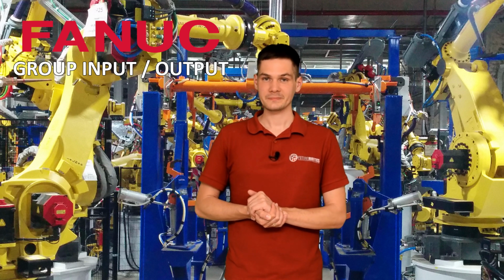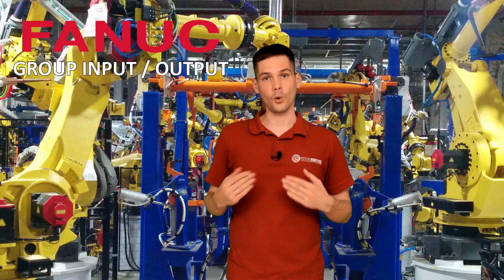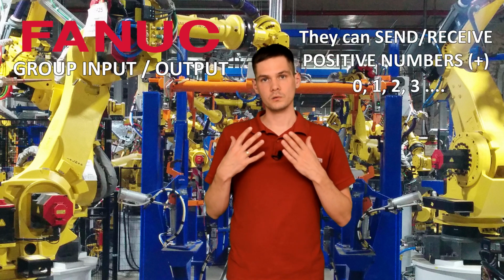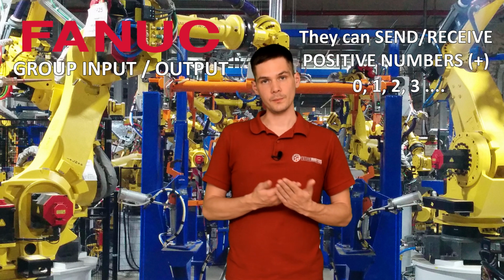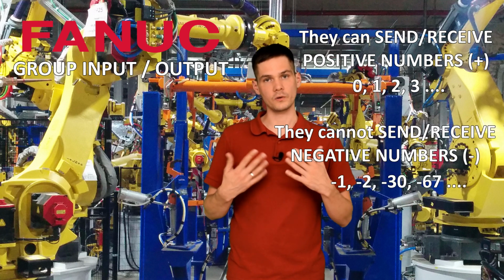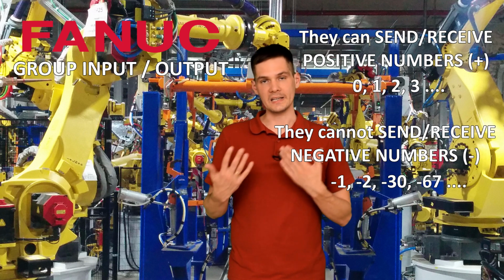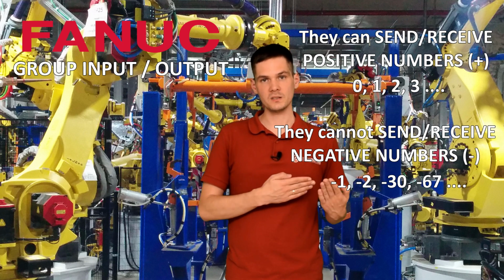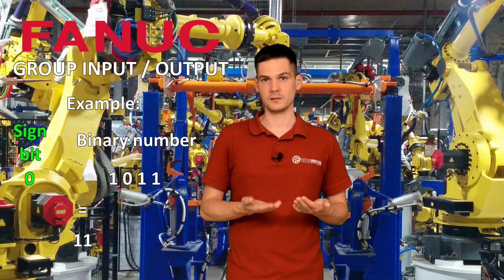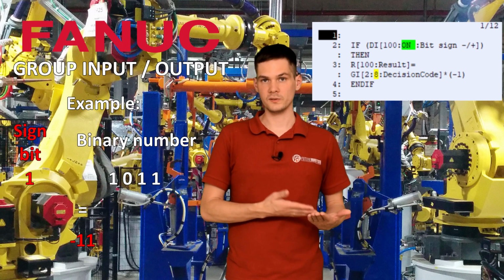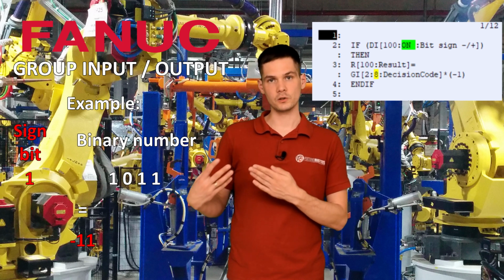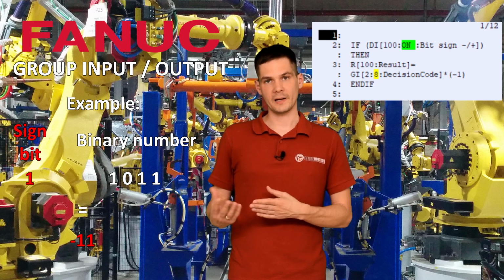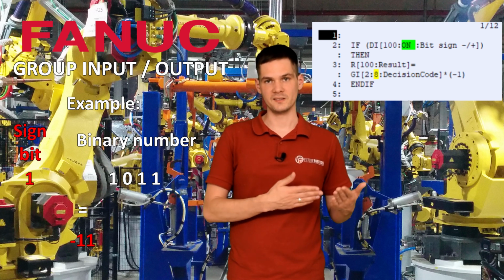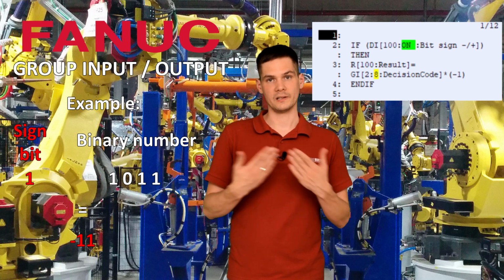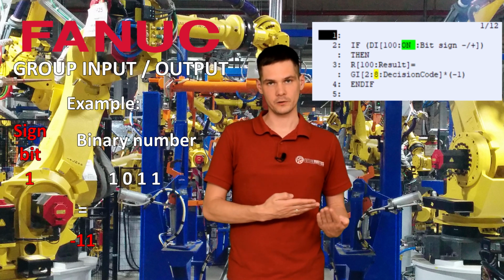It's doable. Also, you can send and receive only a positive number. So the digital group inputs and outputs cannot send or receive negative values. In order to do it, you need an extra bit saying the sign, is it positive or negative, and you need a little bit of extra math to use it later on. Basically the value you get on a group input and output, you multiply by -1 if you get a certain bit. This way you get a positive or negative value.